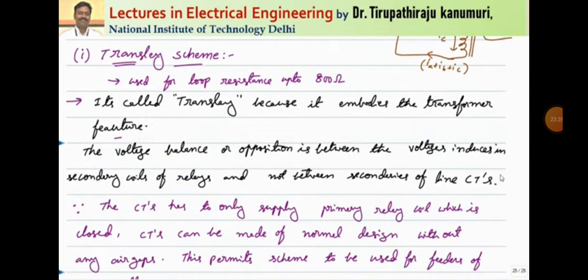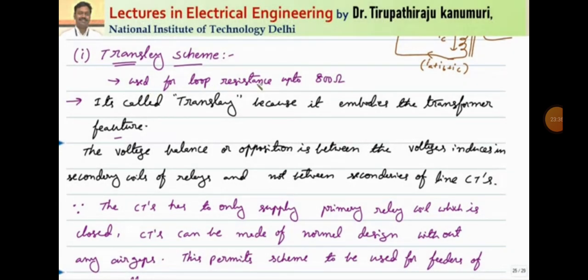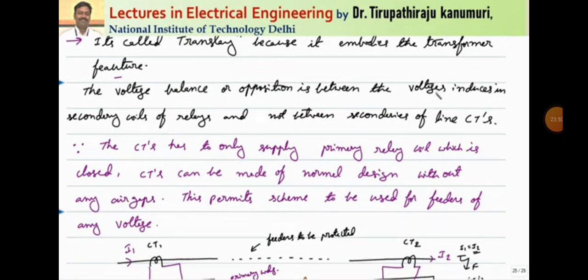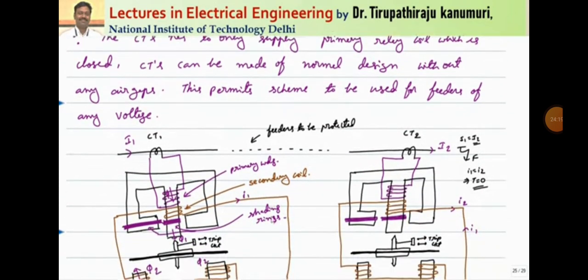Today we are going to discuss the translay scheme; the remaining scheme will be discussed in the next lecture. The translay scheme is used for pilot wire loop resistance up to 800 ohms. It is called translay protection because it employs the transformer feature. The voltage balance or opposition is between the voltages induced in the secondary coils of the relays and not between the secondaries of the line CTs. The CTs are never open-circuited. The CT currents passing through the primary winding are always unaffected, so normal CTs can be used for this purpose.